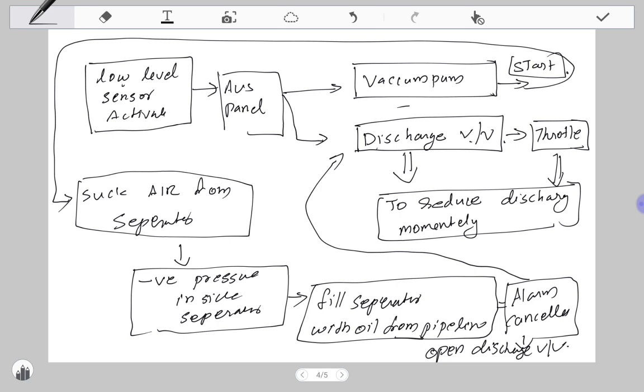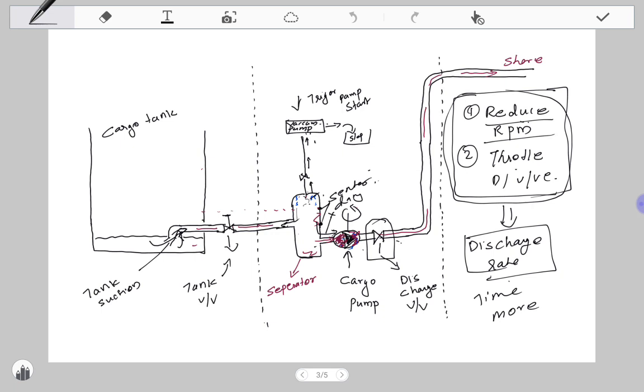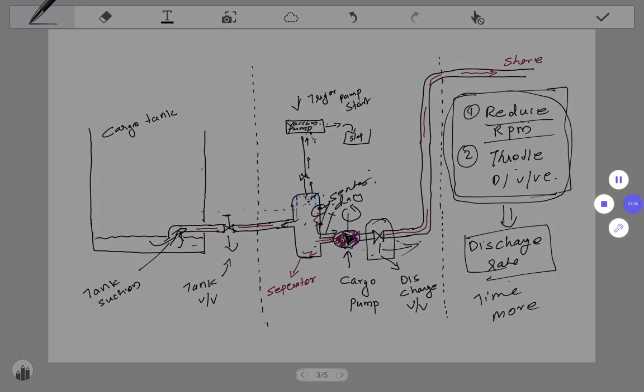The duty officer does not have to keep adjusting the discharge valve and pump RPM to maintain a good flow rate — the job of the duty officer is simplified by this system. In summary: whenever the separator level lowers, the sensors alarm and signal the AUS system, the AUS starts the vacuum pump, vapors are pumped out, more liquid comes inside, and the sensor alarm is cancelled. When the vacuum pump starts the discharge valve throttles, but when the alarm clears and the separator is fully filled, the discharge valve opens again and more cargo flows out.